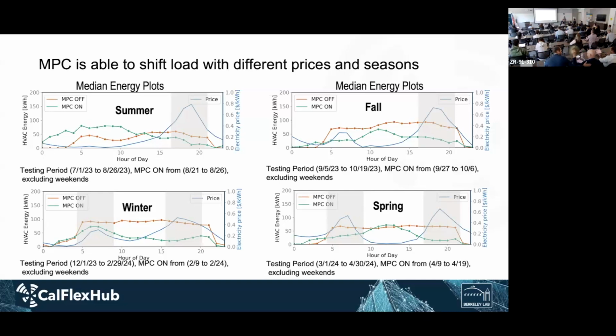And when we were talking about choosing the right building, because this building is served by an underfloor air distribution system, it's able to use a lot of the thermal mass to shift the load. And so, for example, if we look at the summer, without increasing the overall consumption, actually on average decreasing it, we were able to shift a significant portion of the load away in the night doing free cooling or in the morning. And something similar happened in winter where we did preheating, and in spring where we focus more on the central hours of the day.